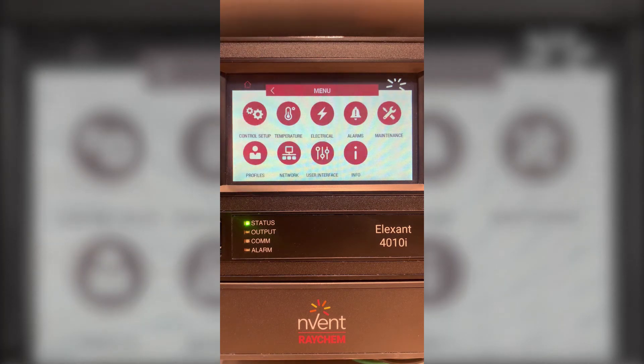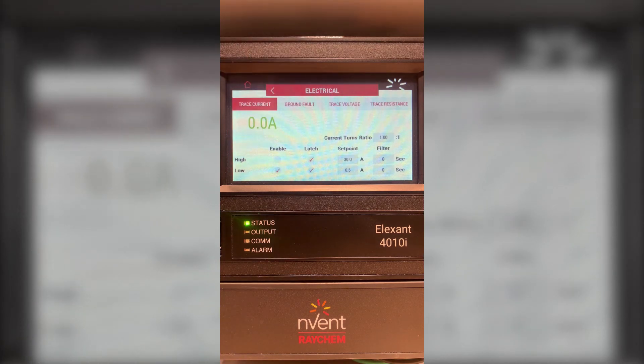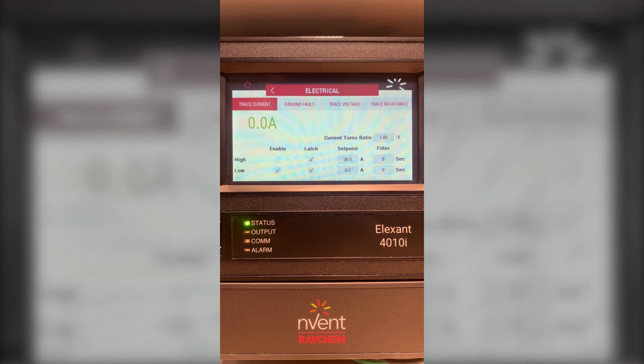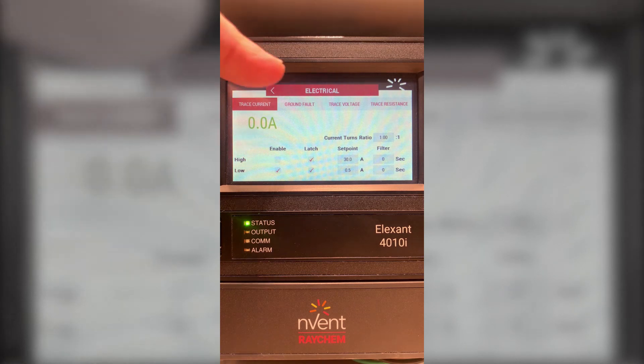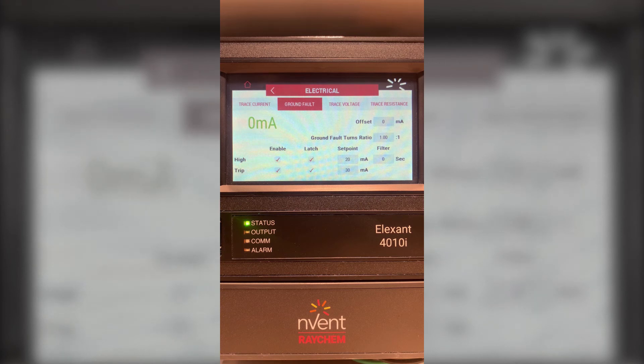Going back to the main menu we'll choose electrical. In the electrical you have your trace current. At the moment I'm showing zero amps because the output is not energized. For the trace current you can have a high current alarm and a low current alarm. These again can be enabled or disabled and latching and non-latching. Next we have our ground fault. By default we have a 20 milliamp high alarm and a 30 milliamp trip. Depending on your application these values can be changed as well as enabled, disabled, and latching and non-latching.